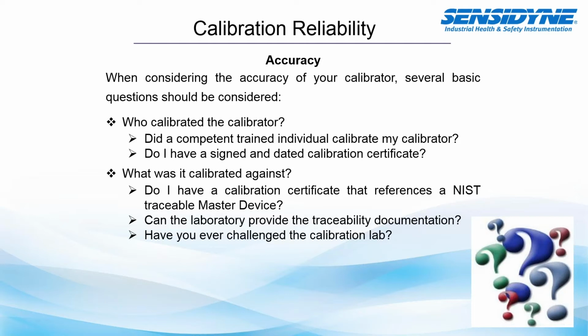So when considering the accuracy of your calibrator, several basic questions should be considered. Who calibrated the calibrator? Ask yourself, did a competent, trained individual calibrate my calibrator? Do I have a signed and dated calibration certificate? What was it calibrated against? Do I have a calibration certificate that actually references a NIST traceable master device? That's something that you should look at on your calibrator's certification. Can the laboratory provide the traceability documentation? Usually that's not included with your calibrator. However, if you call the calibration laboratory, they should be able to provide that traceability documentation for you. And then, have you ever challenged the calibration lab? Make sure that they actually do have that documentation, that it's up to date, and they can actually show traceability.